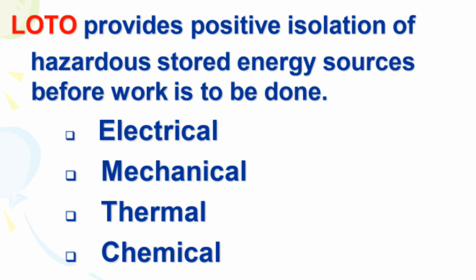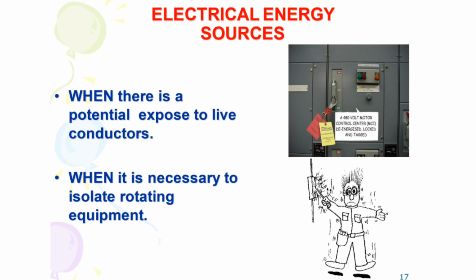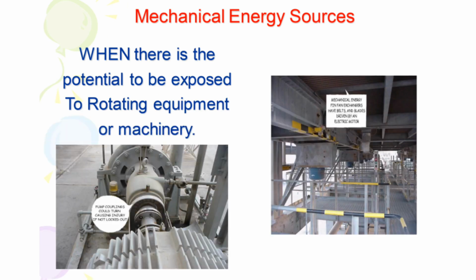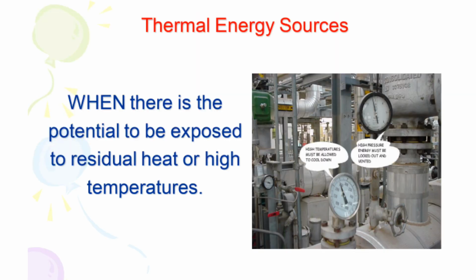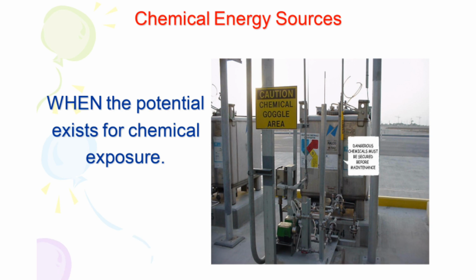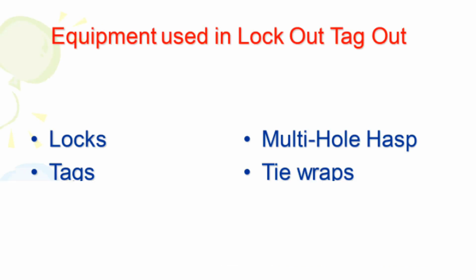Electrical, mechanical, thermal, chemical. Electrical energy sources, when there is a potential of exposure to live conductors, when it is necessary to isolate rotating equipment. Mechanical energy sources, when there is the potential to be exposed to rotating equipment or machinery. Thermal energy sources, when there is the potential to be exposed to residual heat or high temperatures. Chemical energy sources, when the potential exists for chemical exposure.